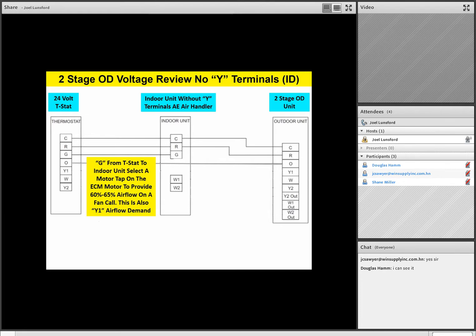And here's how this works, because remember, when the thermostat calls for Y1 operation, or it calls for first stage compressor operation, it automatically, electrically, generates a G call as well. So the thermostat really becomes the main fan control in this example, because anytime you get a Y1 call, you're also going to generate a G call. And so if we set our G airflow up on the indoor unit at 60 to 65% airflow for that first stage of cooling, we're going to automatically have 60 to 65% airflow on a Y1 call. Does that make sense to everybody?